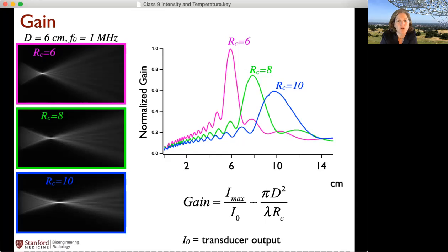Another one that's really important to notice is that as you increase the focal depth, as you go from a focal depth of 6 centimeters to 8 and 10, then the focal spot increases. Sometimes you're just stuck with what your focal depth is in order to get to your target, but it's just one of those trade-offs to keep in mind.